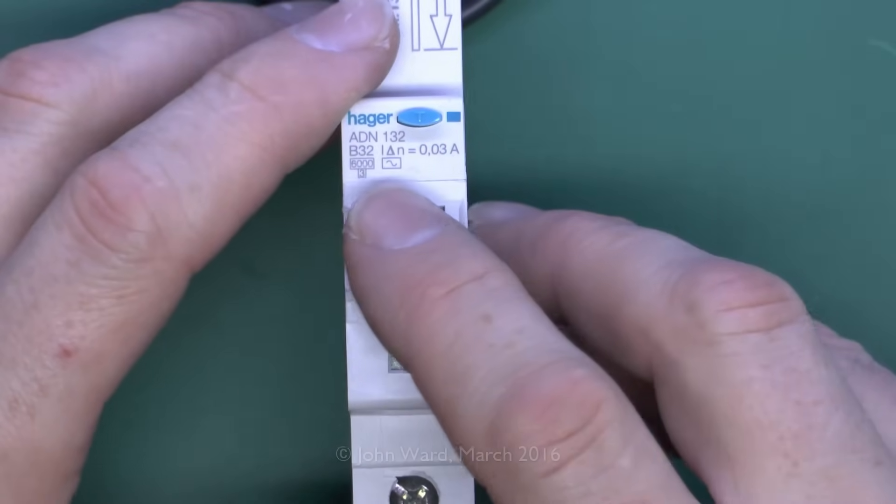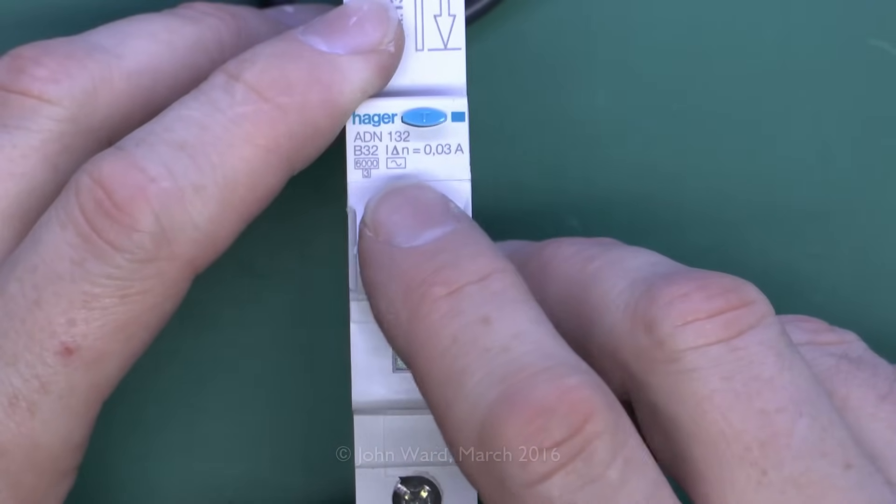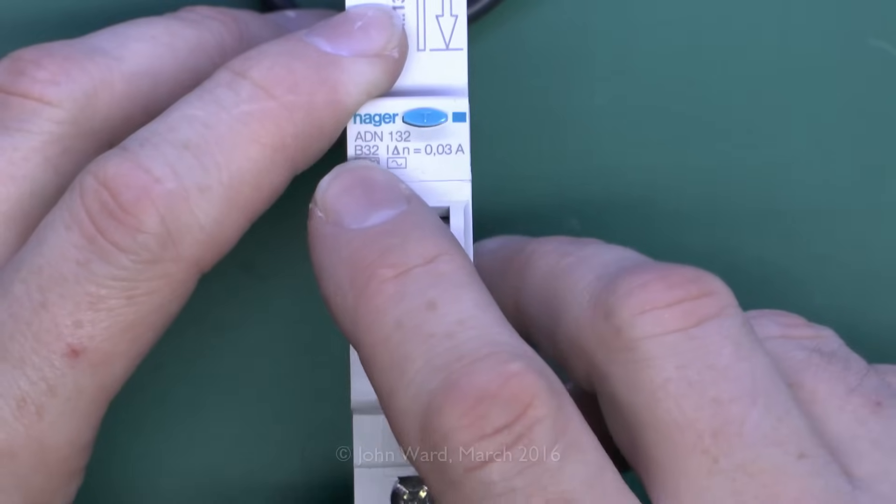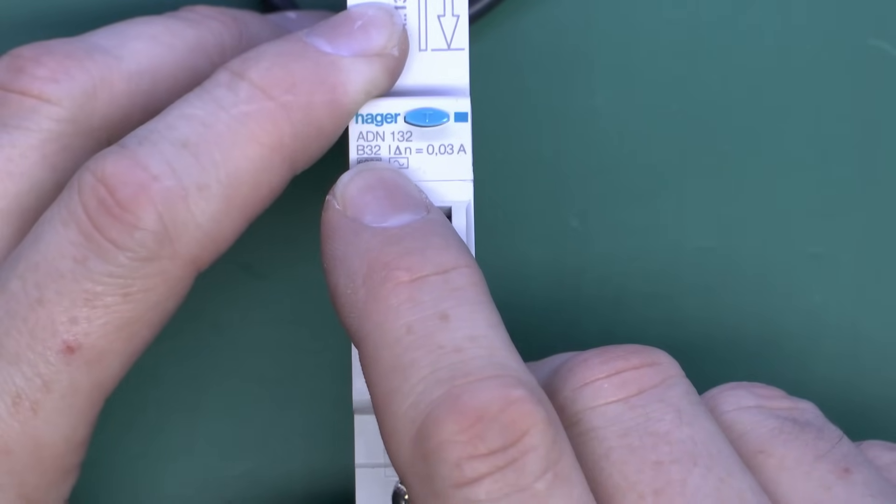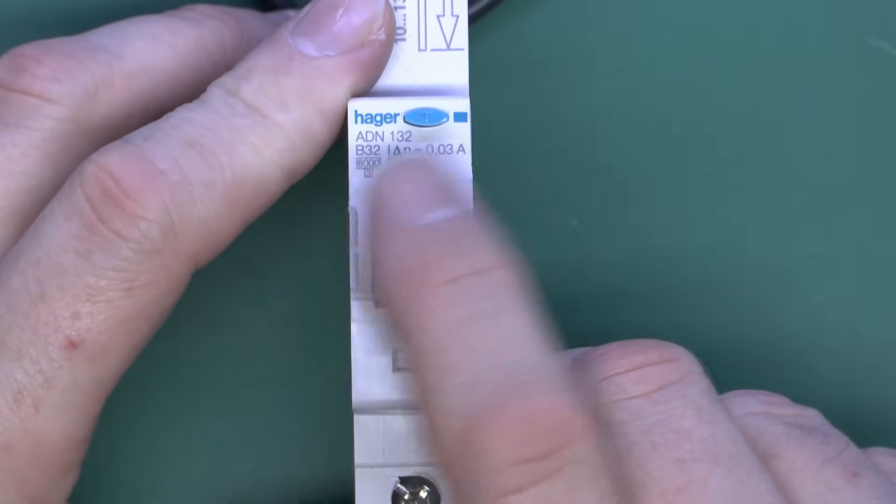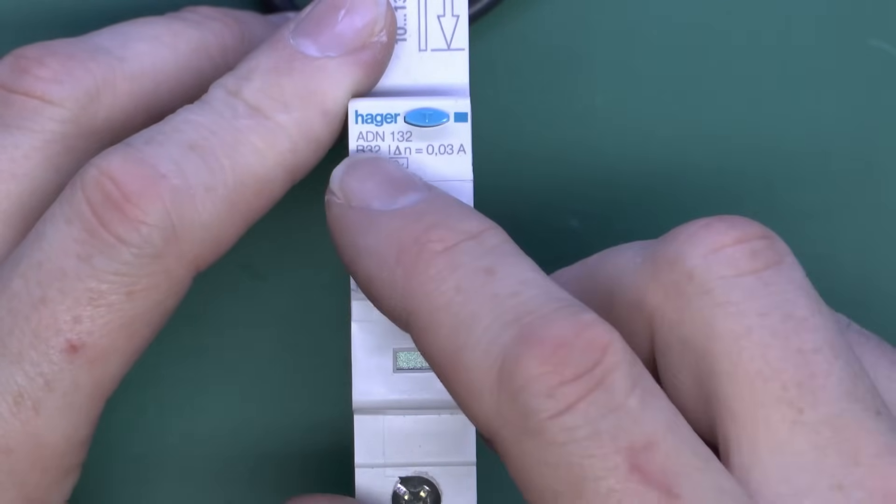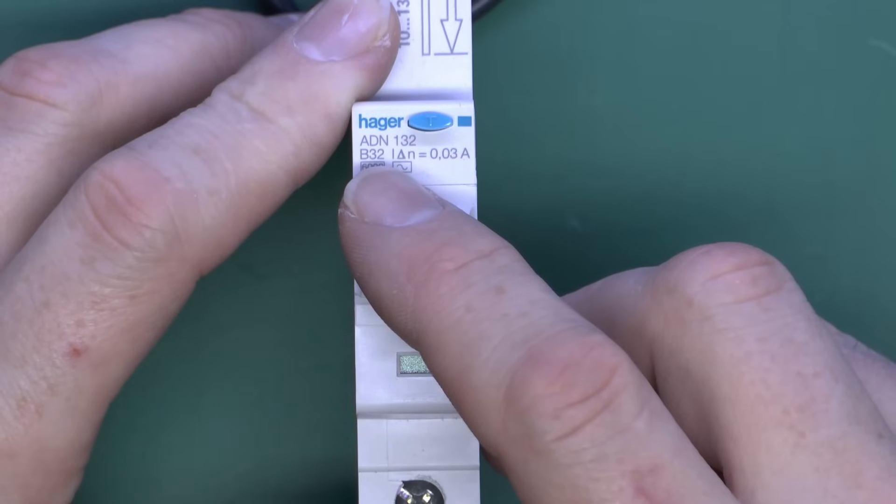Now, have a look on the front of the device, and you see it's got the markings really for both of the components there. We've got the rating here, which is a type B and 32, so it's 32 amps in this case, and that refers to the circuit breaker part, so essentially it's just a normal 32 amp circuit breaker.